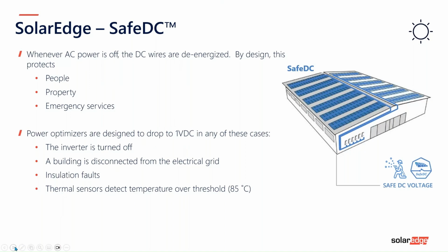Turning the inverter off starts SafeDC. So does the arc fault detection, or the buildup of heat around the optimizer. The optimizer has a thermal temperature sensor on it, or the Sense Connect, which is on the optimizer, which is measuring the heat around the connector. As soon as any of these things alert, or insulation faults, they all go back down to 1 volt. So any of these would trigger the SafeDC.